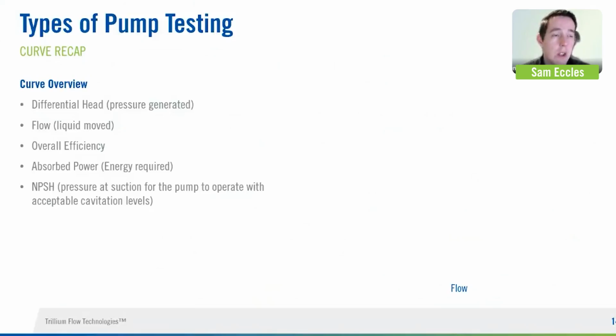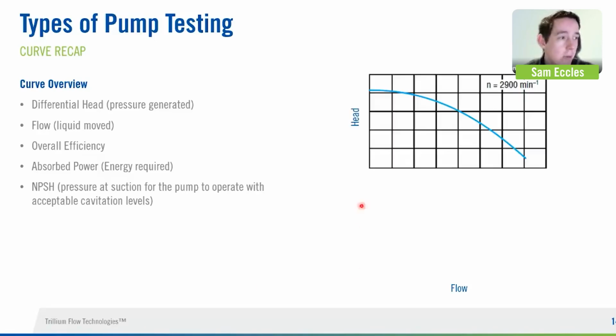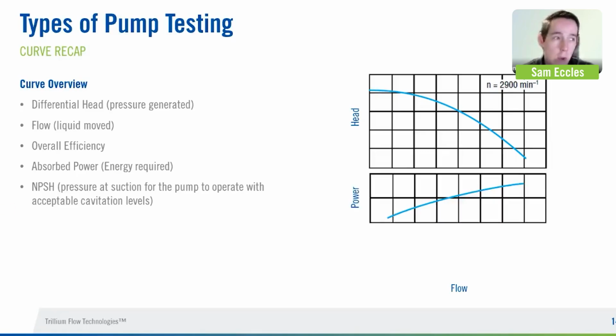Okay, so very quickly, I'll just set up for Massimiliano. So if we talk about the types of pump testing that we have. So what we really want to cover here is just what we're looking at as a performance curve. So what are we trying to get? So you have flow horizontally and pressure or head on the vertical axis. What we're trying to do on a performance test is sweep through an agreed number of points along this curve to prove out that we are hitting the required flow and head. That's the number one check we're trying to do.